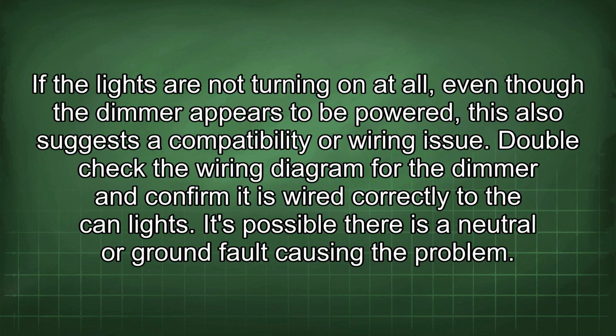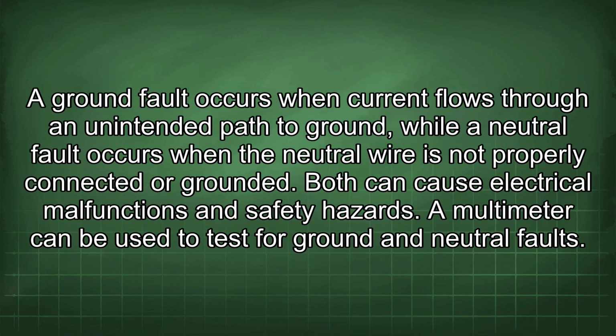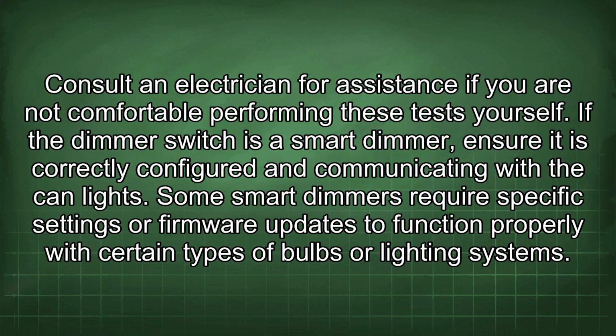If the lights are not turning on at all, even though the dimmer appears to be powered, this also suggests a compatibility or wiring issue. Double-check the wiring diagram for the dimmer and confirm it is wired correctly to the can lights. It's possible there is a neutral or ground fault causing the problem. A ground fault occurs when current flows through an unintended path to ground, while a neutral fault occurs when the neutral wire is not properly connected or grounded. Both can cause electrical malfunctions and safety hazards. A multimeter can be used to test for ground and neutral faults. Consult an electrician for assistance if you are not comfortable performing these tests yourself.